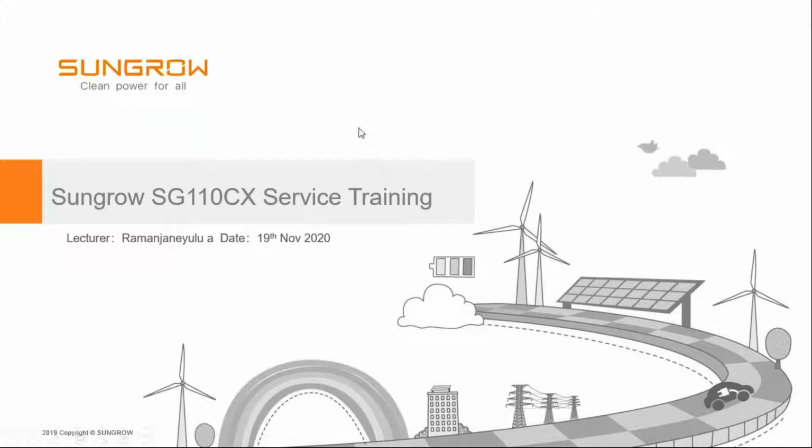So welcome everyone. This is a small session basically to cover the commissioning part as well as a bit on the product and the basic steps which you need to consider before installing and commissioning the inverters, especially this SG110CX. As you know, the CX version is all about a 1000 volt system. That is, on the DC side it will be 1000 volt. On the AC side, the voltage will be 400. So let me go through.